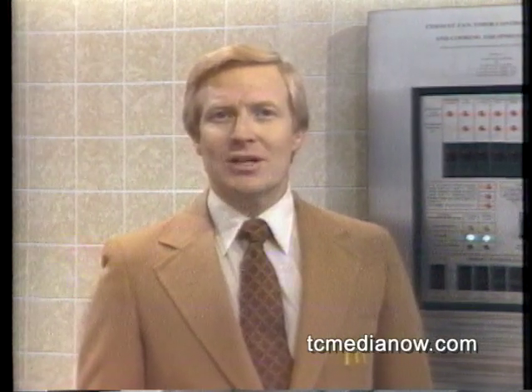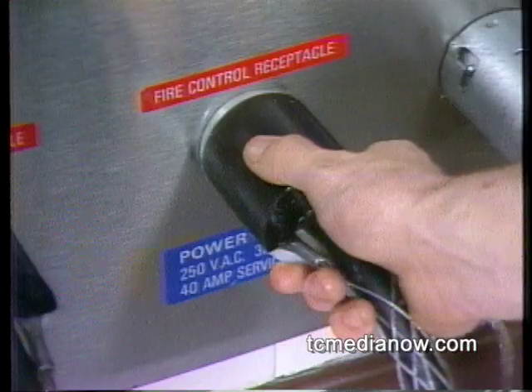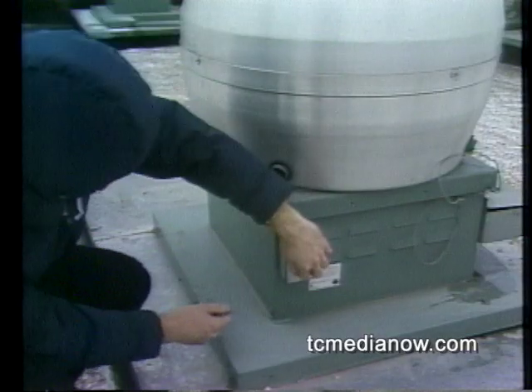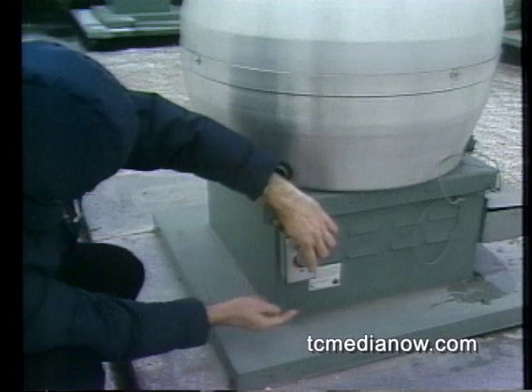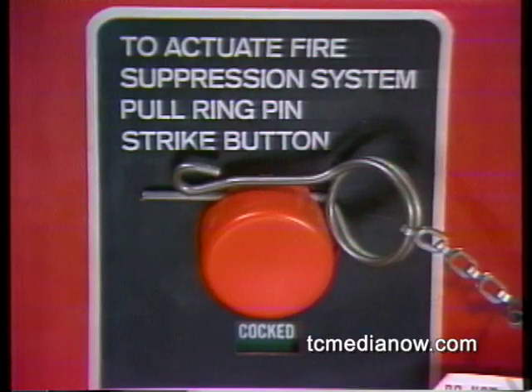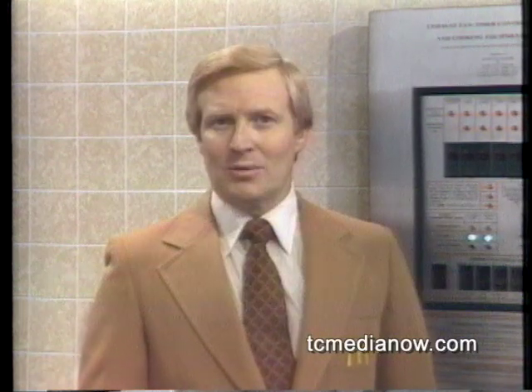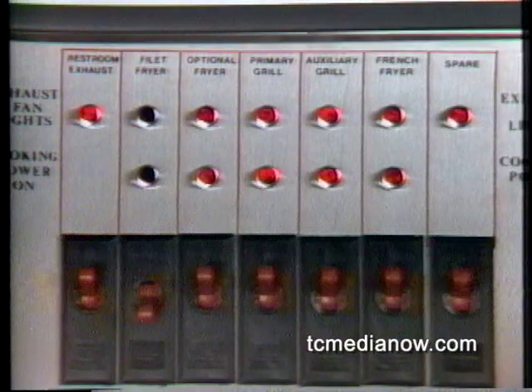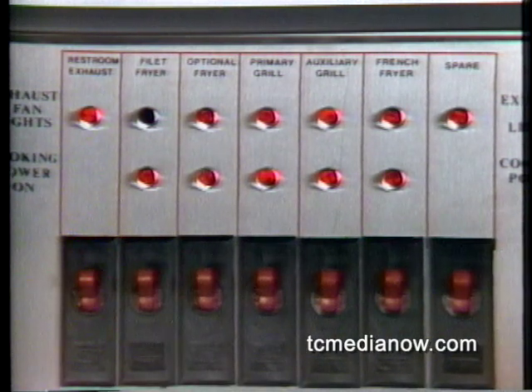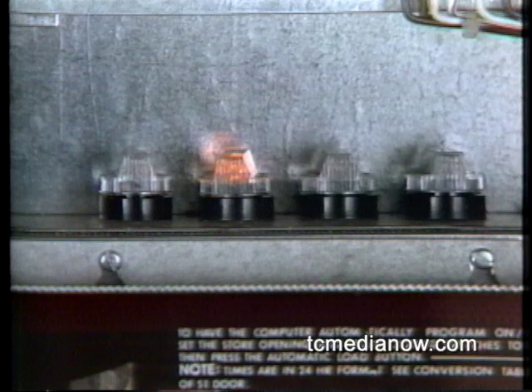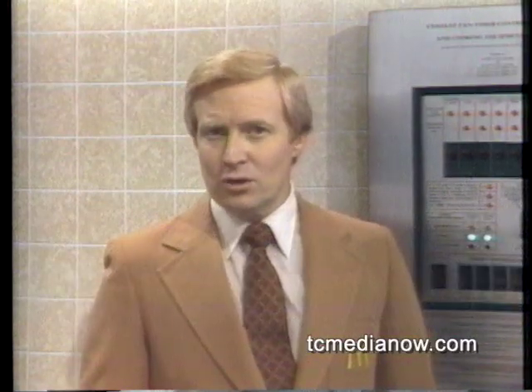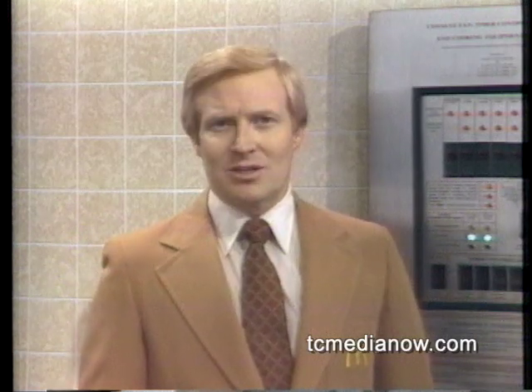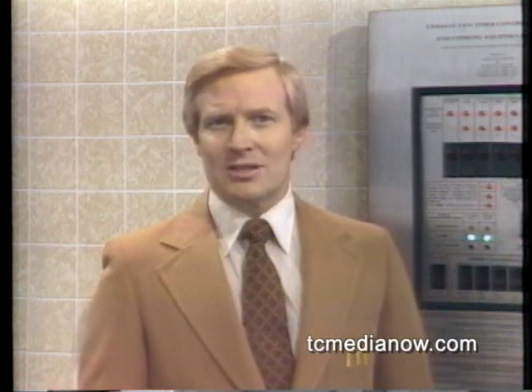Before requesting service, check these 3 things. Is the cooking unit plugged in? Is the disconnect switch on the exhaust fan in the on position? Is the Ansul system cocked and reset? These are the 3 most likely problems when cooking equipment fails to go on in energy interlock system operation. If the circuit light is not lit, check the circuit breakers and fuses in the interlock panel. A light on the fuse cap indicates a bad fuse. If the circuit breakers and fuses are good, the trouble is in the energy interlock system, and you should request service on the interlock system.